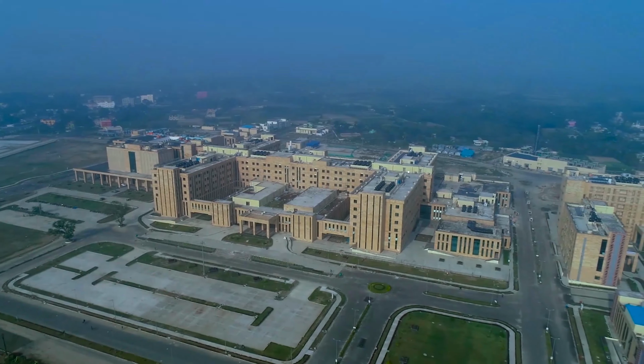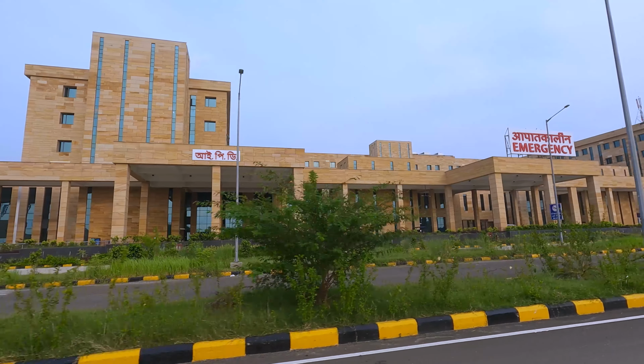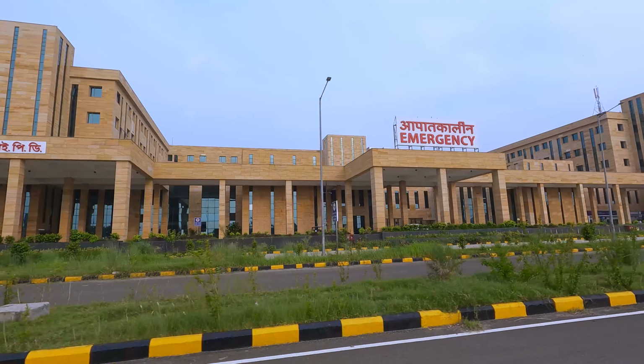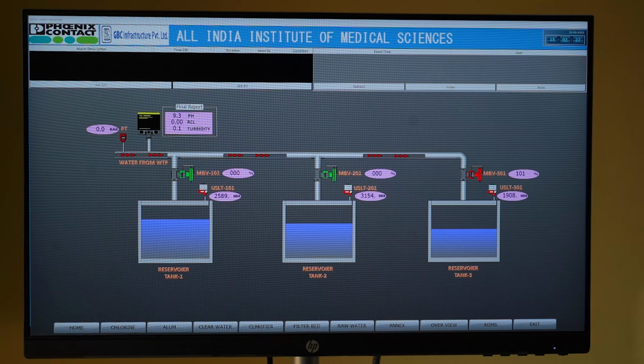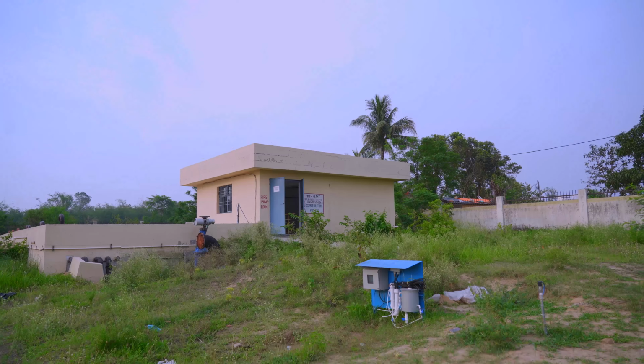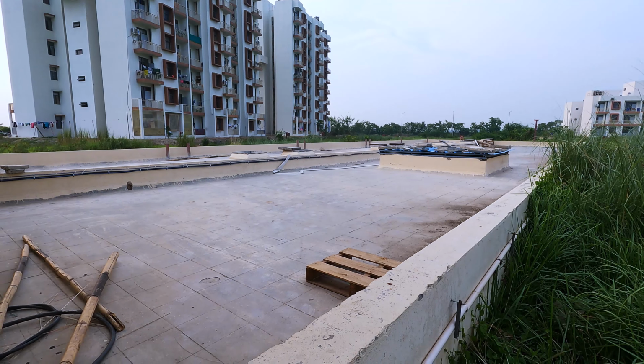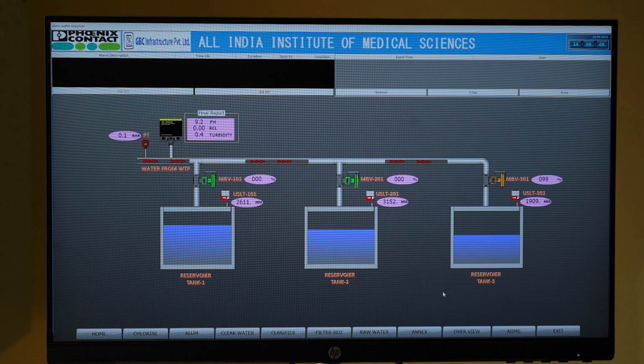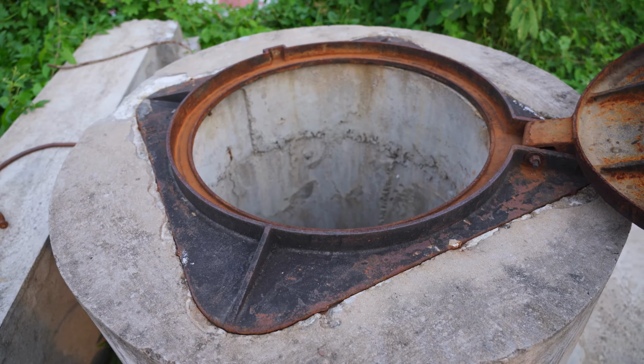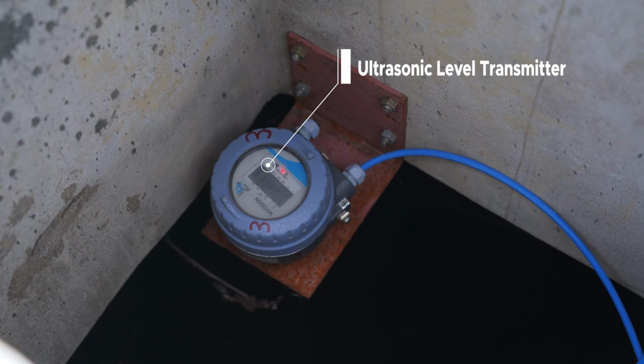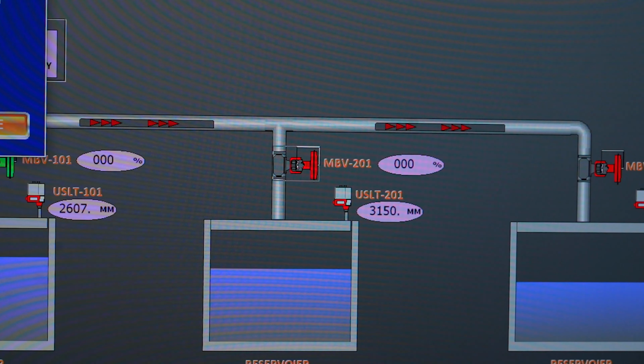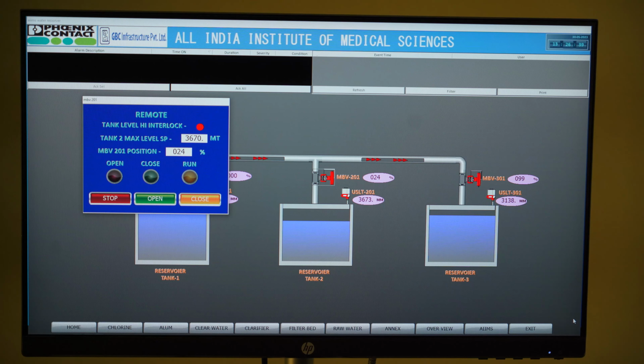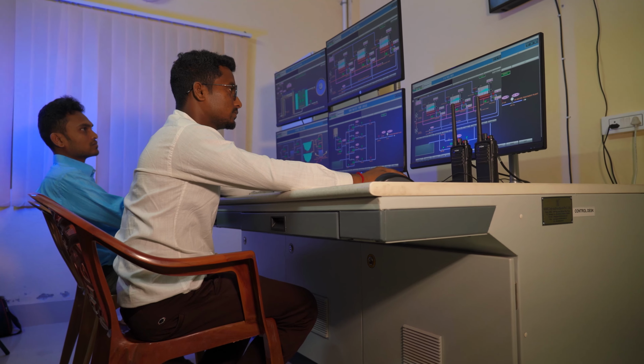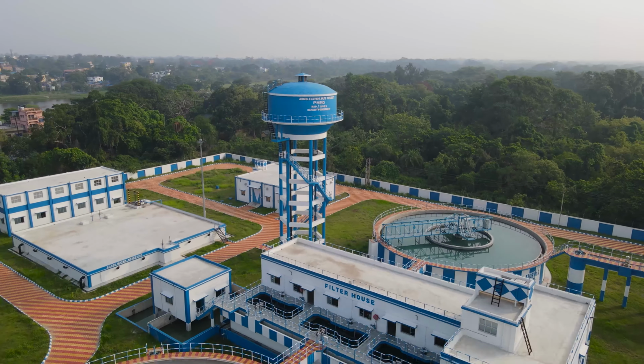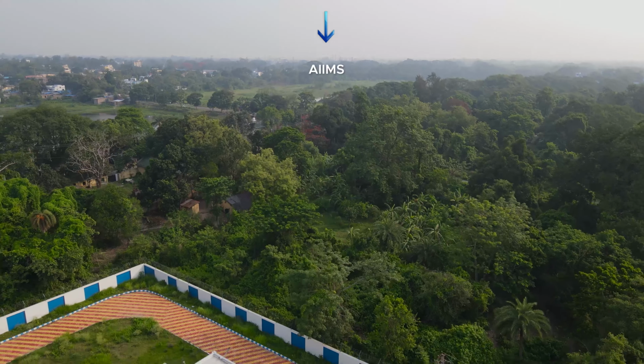Now the raw water is ready to be delivered to AIIMS hospital, the end user. At AIIMS, there are 3 ground level reservoirs to be filled with treated water. The 3 GLRs are situated at 3 different places, 500 meters apart from each other. The level of water in the reservoirs is continuously monitored by non-contact ultrasonic level transmitters, and the flow of water is controlled in each tank through actuator-controlled motorized delivery valves remotely from the SCADA control room over a distance of 15 km through a wireless communication system.